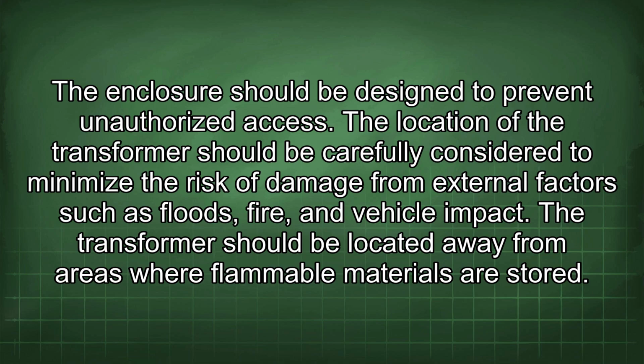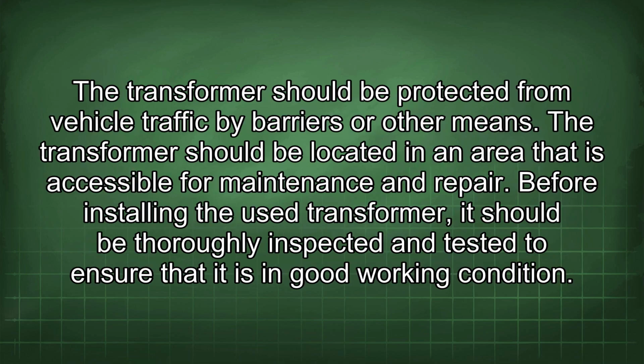The location of the transformer should be carefully considered to minimize the risk of damage from external factors such as floods, fire, and vehicle impact. The transformer should be located away from areas where flammable materials are stored. The transformer should be protected from vehicle traffic by barriers or other means. The transformer should be located in an area that is accessible for maintenance and repair.